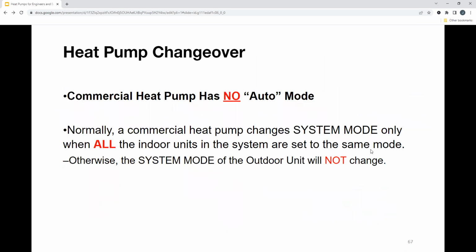Okay, last 2 topics under this section is heat pump changeover. So we don't talk about this a lot. Typically we talk about a simultaneous system, which Alex mentioned is one of the more popular commercial heat pumps, right? What you do is you set that to auto mode, and it adjusts in about a 2-degree span and chooses whether it needs heating or cooling in the space. All the occupant needs to do is set the temperature that he or she wants.